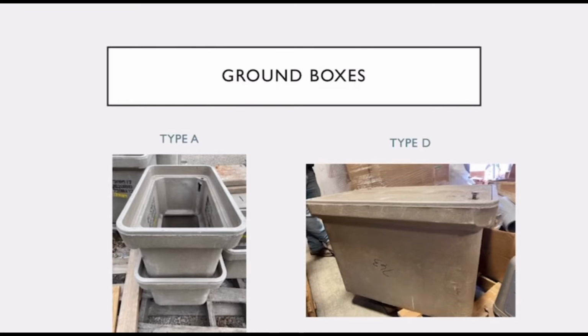The Levy Company currently uses ground box type A, which is a smaller box of 12 inches wide by 23 inches long and 11 inches deep that we typically use for illumination installations. There is also a ground box type D. This is a larger box at 16 inches wide by 29 inches long and 22 inches deep that is typical for traffic signal installations.